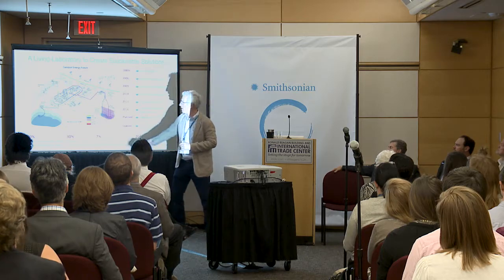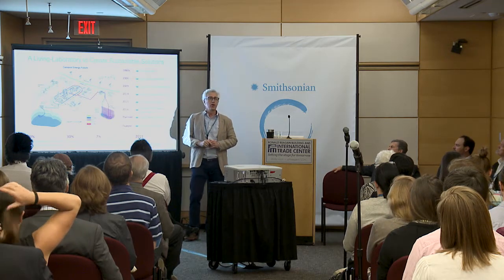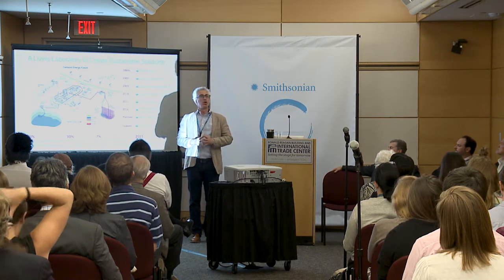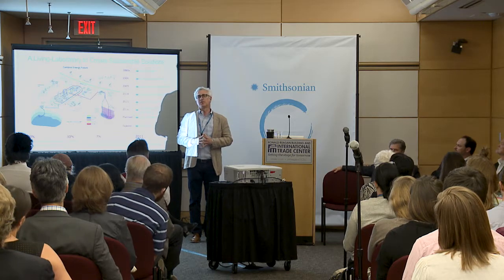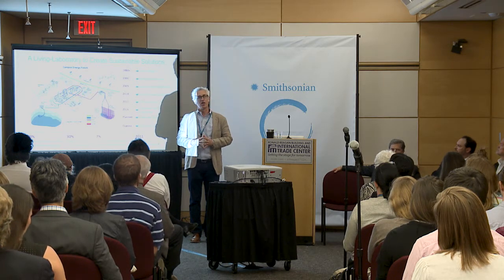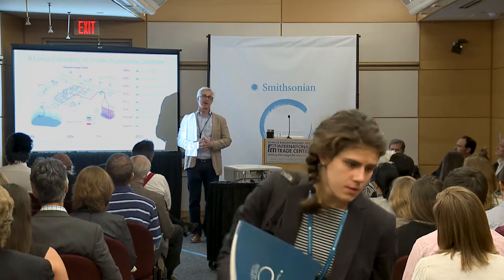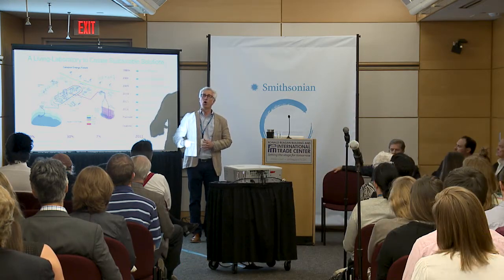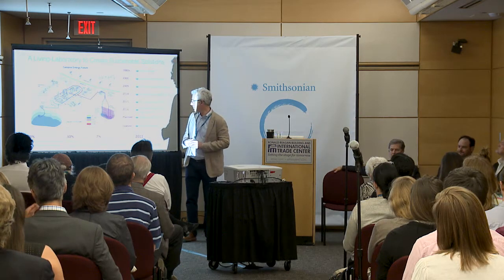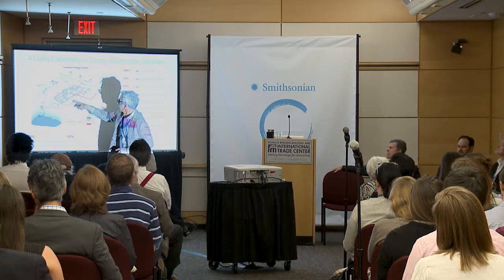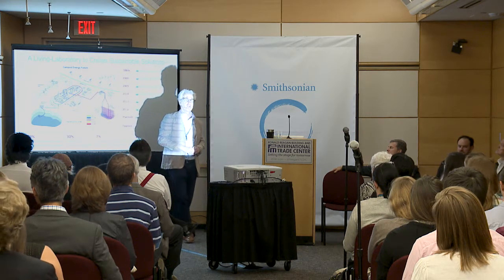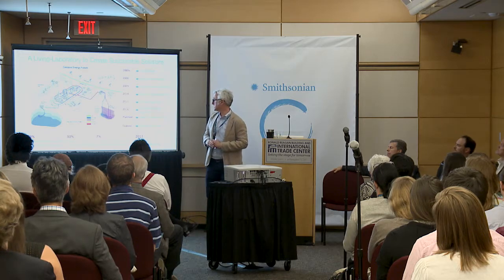I'll show a picture of that in a minute—you can see it over here in the left corner. 270 feet below the surface of Cayuga Lake, an important body of water in Ithaca and to Cornell, the water temperature is always below 45 degrees. We circulate that water open loop through a set of heat exchangers on the shores of the lake, and it cools a district cooling system for the university, providing all of our cooling needs.